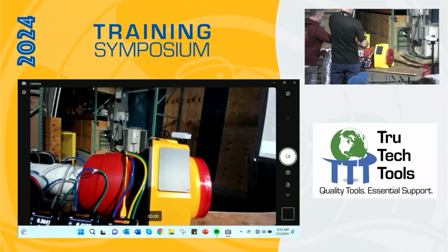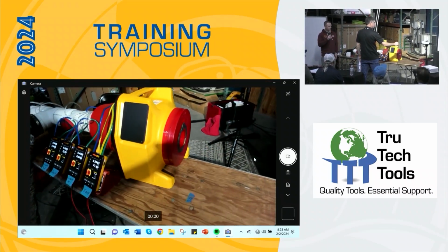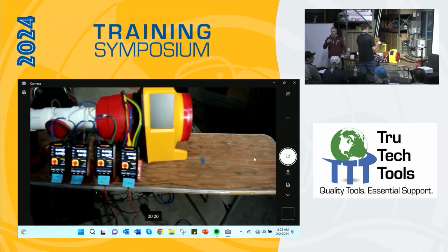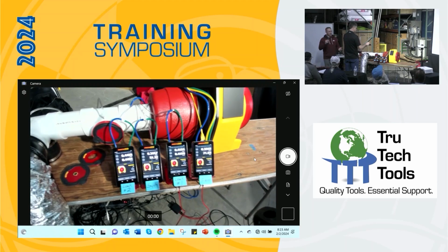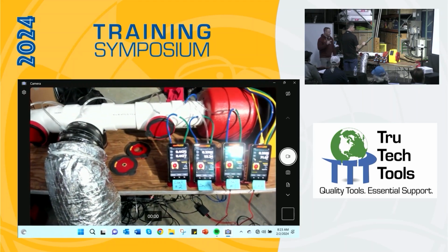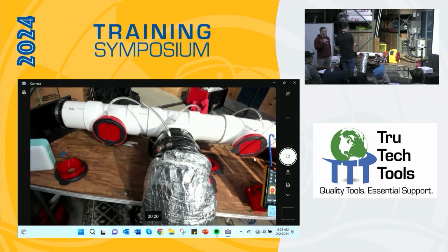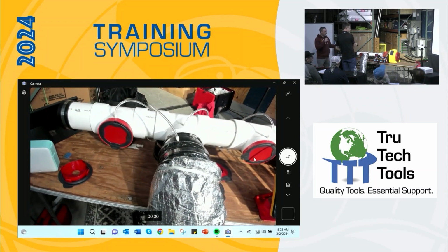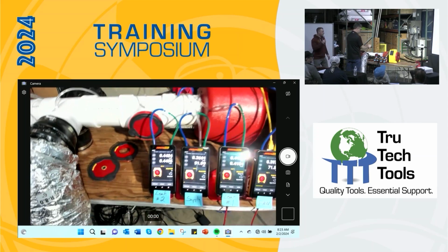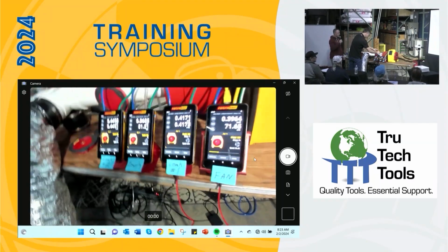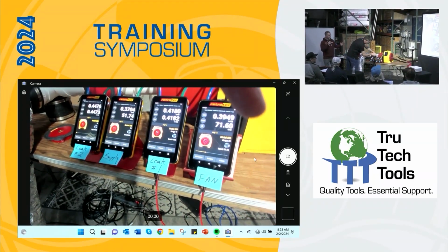Thanks, Eric. So, Eric had this idea for a presentation we could do. He said, let's have a duct that goes out into the audience and do stuff with it and see what happens, to show what happens in a poorly insulated duct system versus a good one. So I mimicked a trunk line and a supply that would behave similarly to what we would see in the field. This fan that we're using, if you've never seen one before, is a duct tester. We use this to measure leakage in ductwork. But here it's our air handler fan.